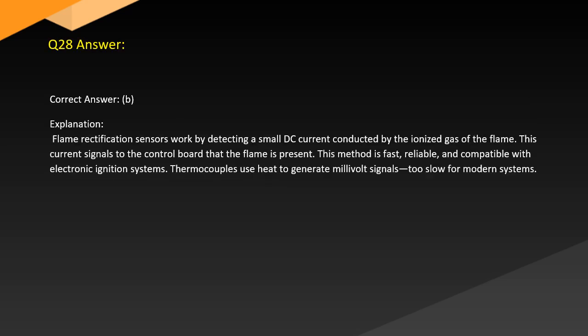Answer. Correct answer, B. Explanation. Flame rectification sensors work by detecting a small DC current conducted by the ionized gas of the flame. This current signals to the control board that the flame is present. This method is fast, reliable, and compatible with electronic ignition systems. Thermocouples use heat to generate millivolt signals. Too slow for modern systems.